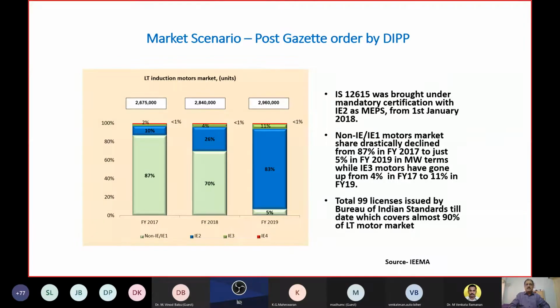Also importantly, the Government of India came with the suggestion that all motor manufacturers should punch the ISI mark of the BIS. So this also helped us to limit the number of motors that will get imported in India. India was an importing ground. So that was limited primarily because most of the manufacturers outside the country, except one or two in China, did not come up to get their motor plant tested by the Bureau of Indian Standards and approved by the Bureau of Indian Standards for marking their motors with ISI.